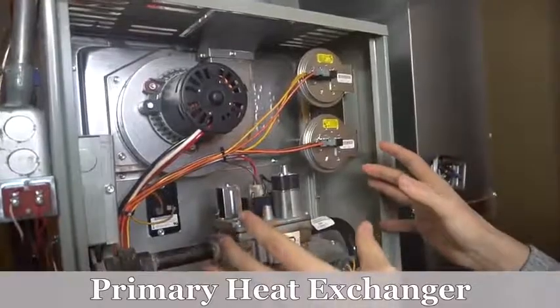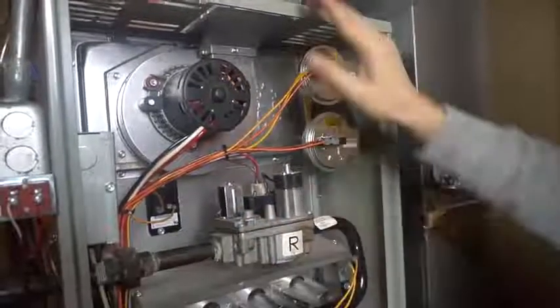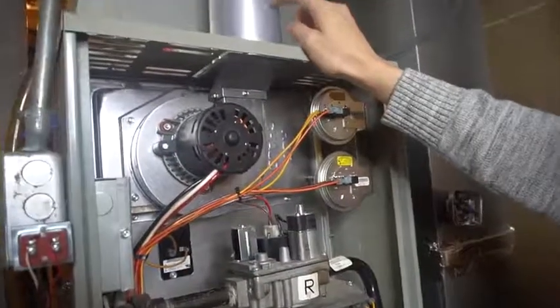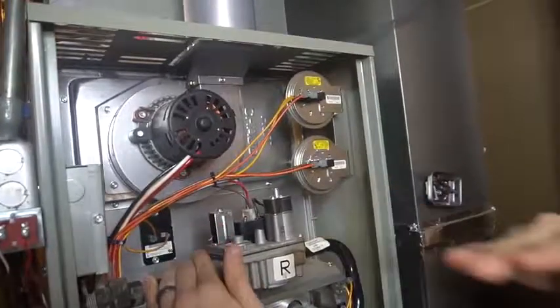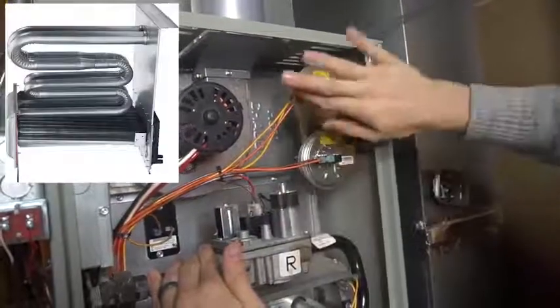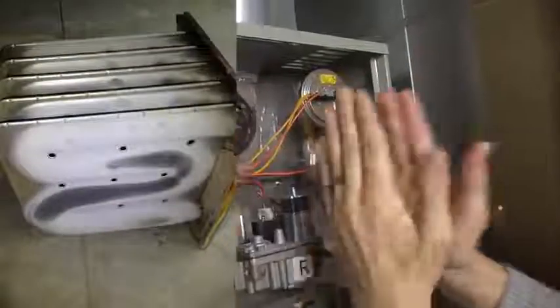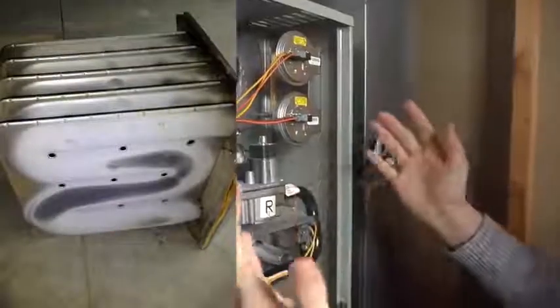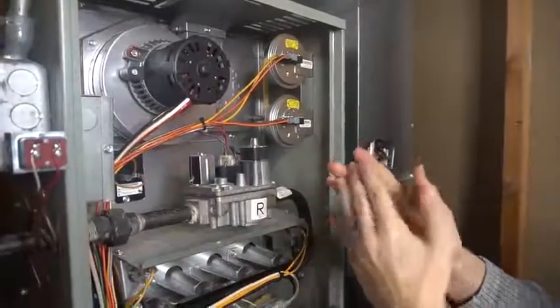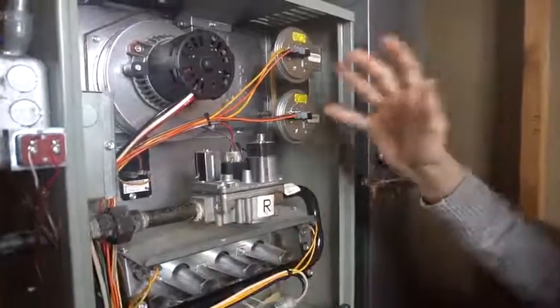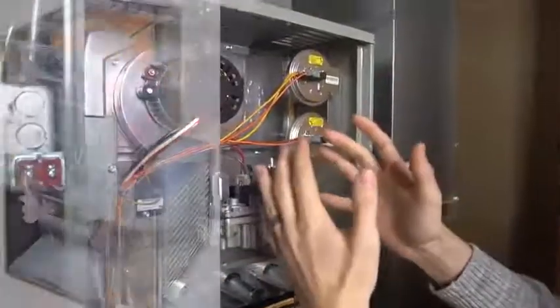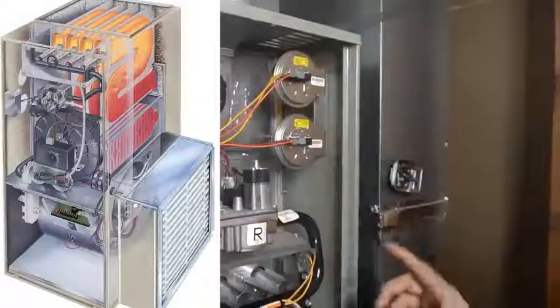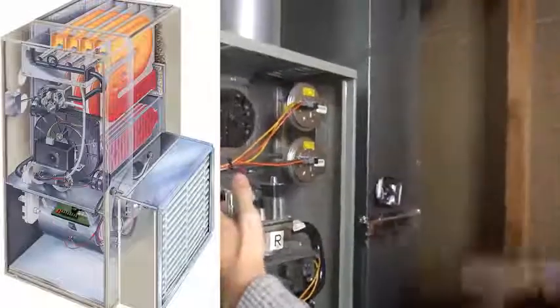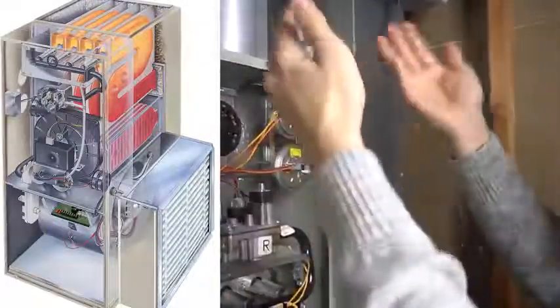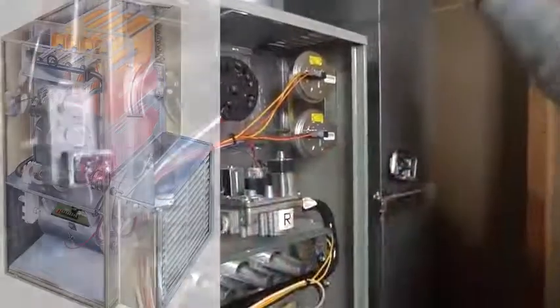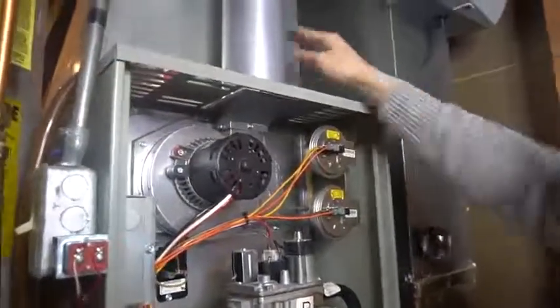That is what separates your house air from the combustion gases going out the exhaust pipe right here. And that heat exchanger is usually either tubular, where it snakes back and forth, or it's divided into cells. And like I stated previously, the purpose of that is to divide the house air from the combustion air and also to give off heat. So that heat exchanger heats up real hot and your blower fan is constantly circulating air.